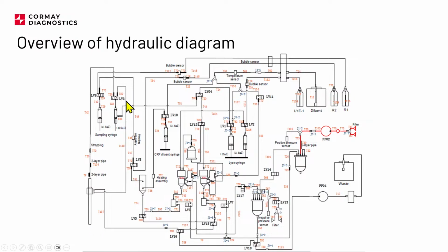We also have this valve 3, and you can see that this is directly connected to the rinsing head. So through this part of the circuit, we are also supplying diluent to the rinsing head, because we also want to clean the outside surface of the sampling needle right after blood was aspirated or transferred from here to here, right? Because if we put the sampling needle into the sampling tube, there will be a lot of blood on the outside. So this needs to be cleaned.